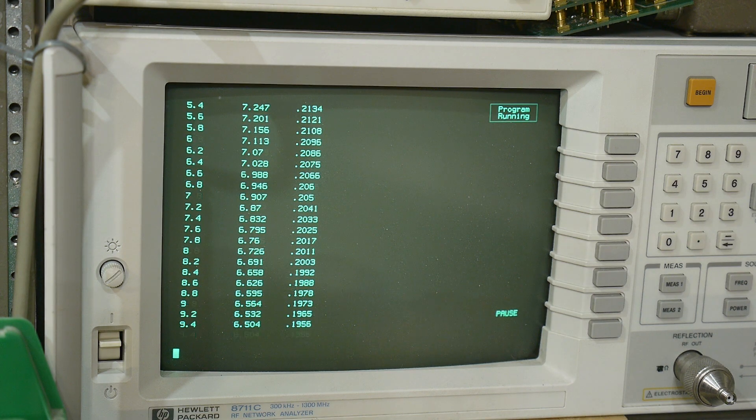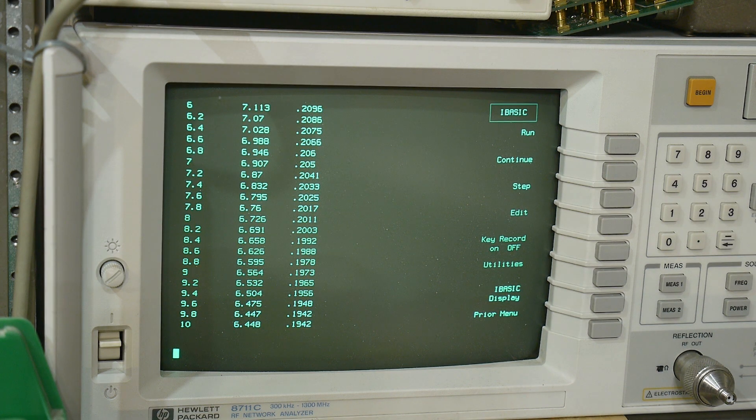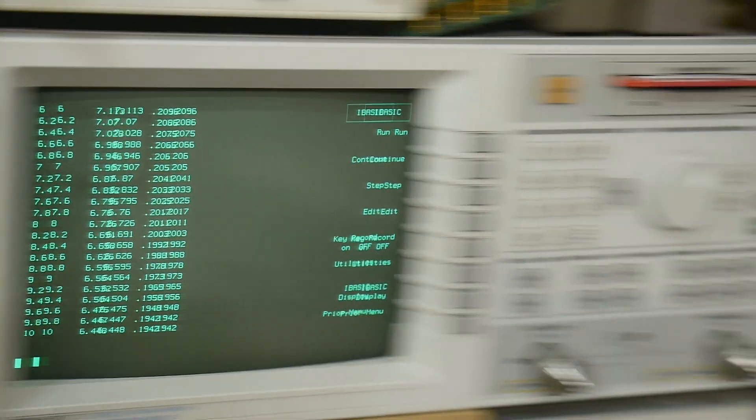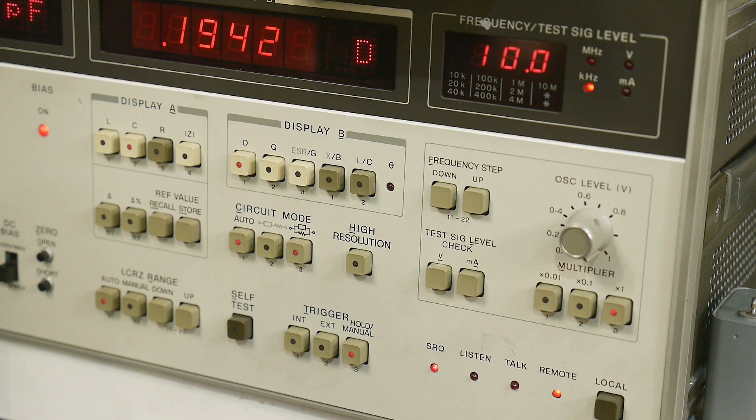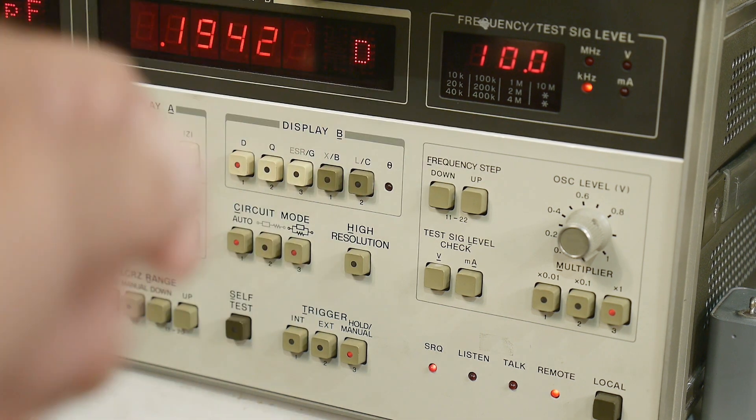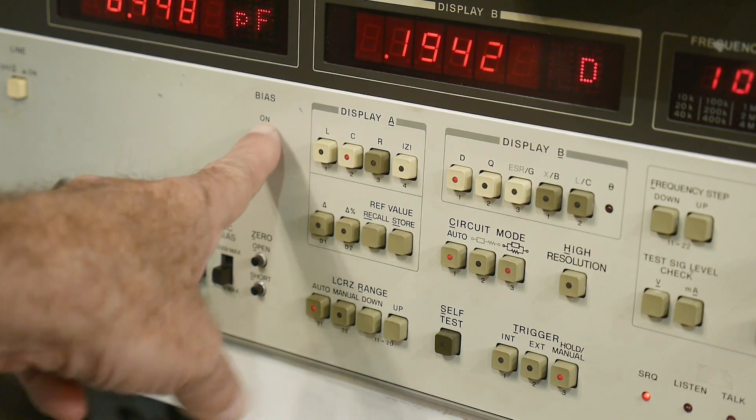And, yeah, so it's controlling the other instrument just fine. When you talk to the instrument, you get a remote light and a service request light on. When you flip the switch in the back, you get the DC bias on, so you know you're applying DC bias.